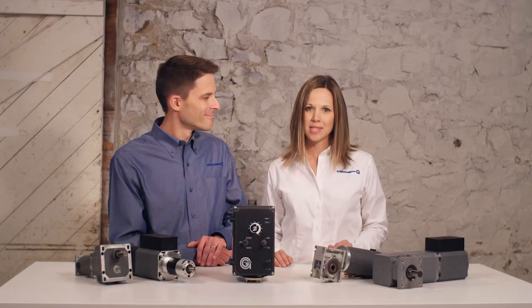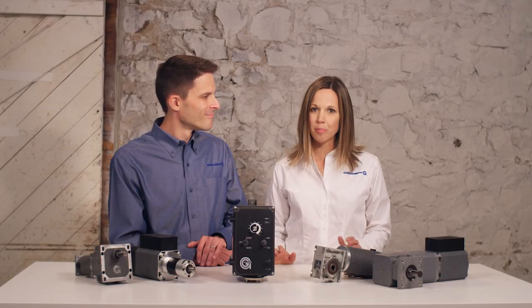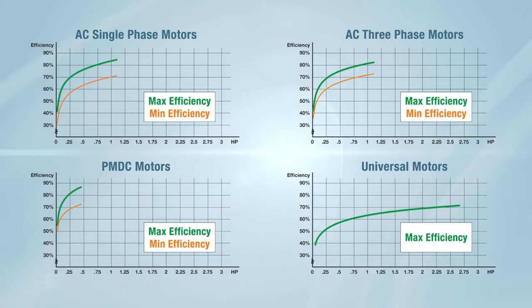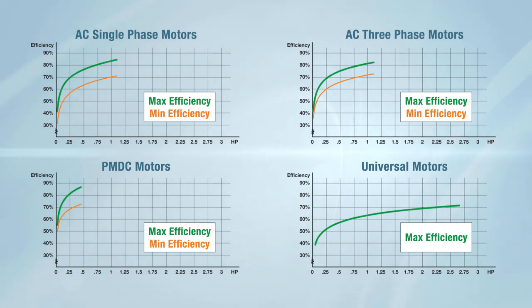Next, we want to share several efficiency curves with you. The first set includes each of the four motor types we've discussed to help you calculate current draw. These curves can be used together with the formulas or STP calculator to estimate the amp draw within your application. Most of these graphs show two curves to represent the high and low efficiency range for each motor type.